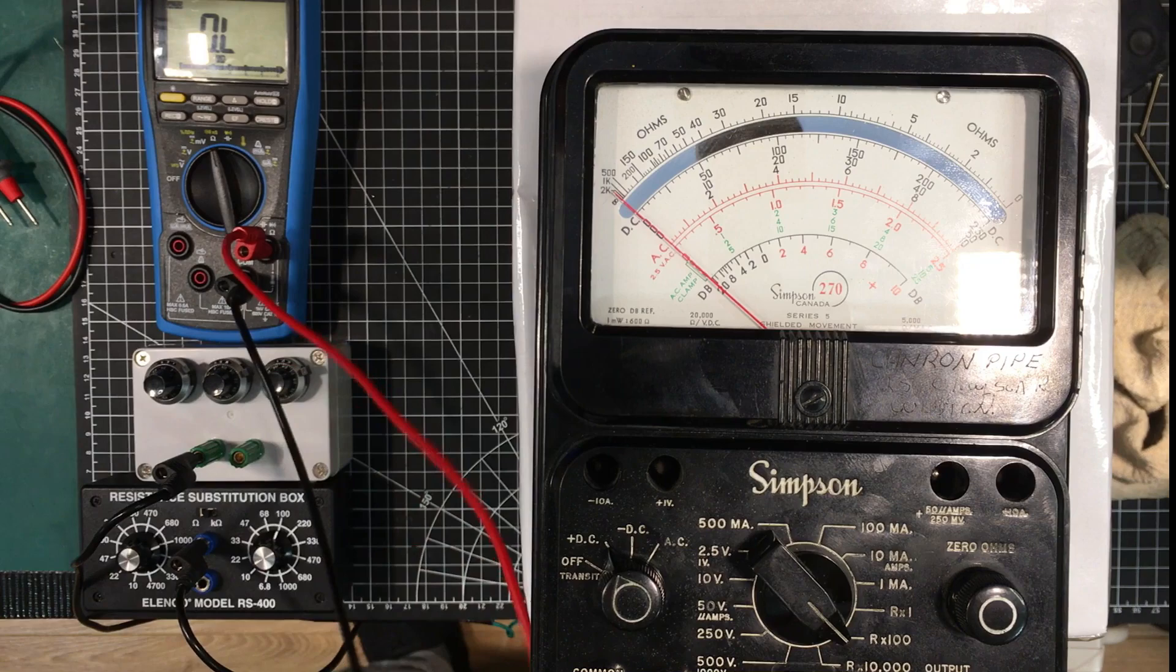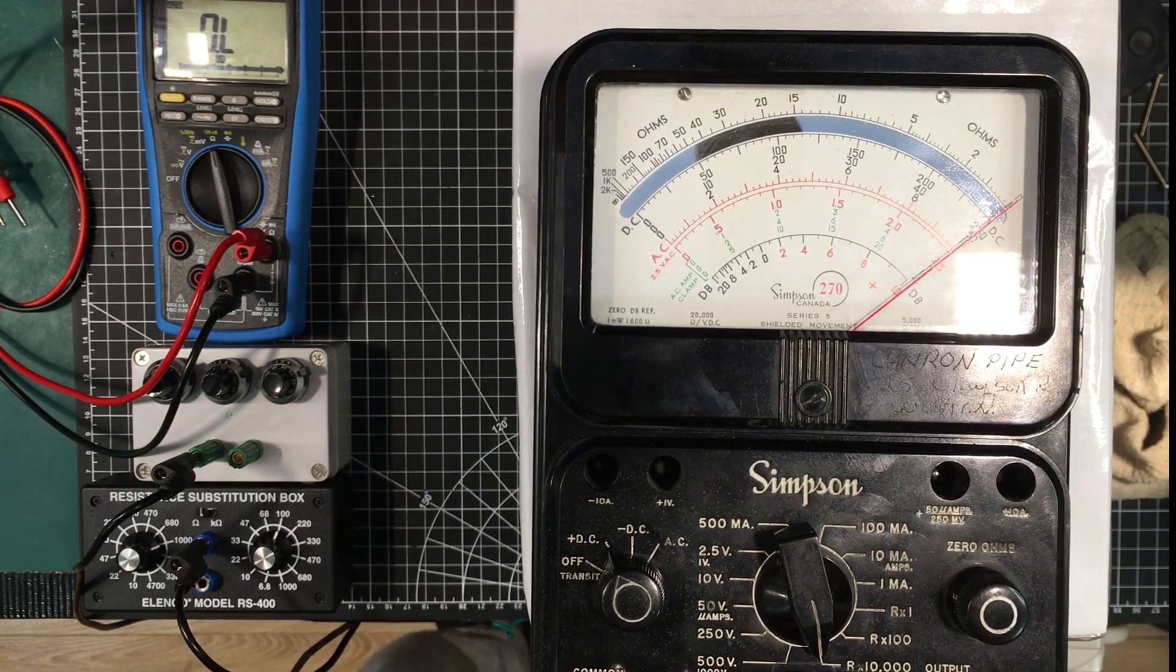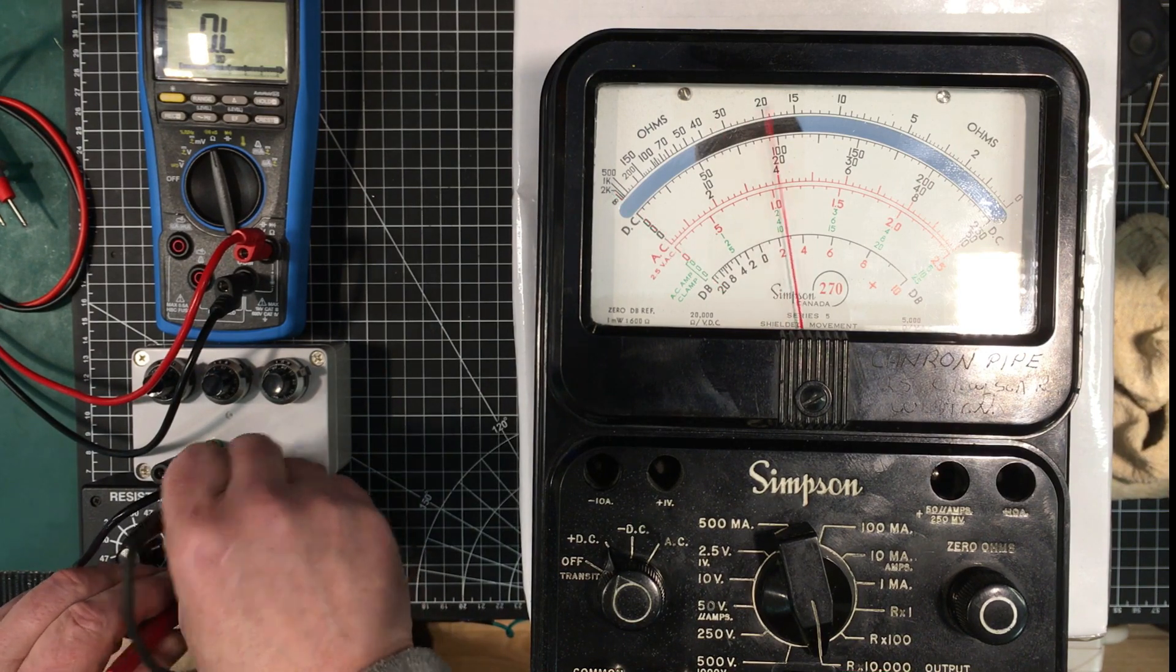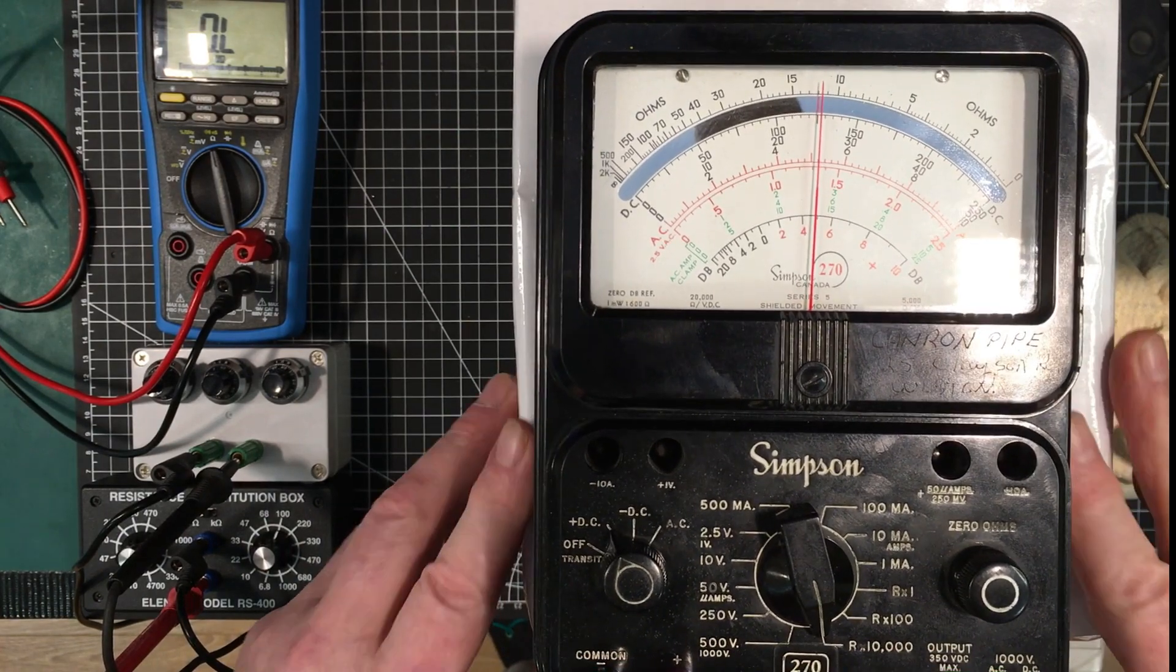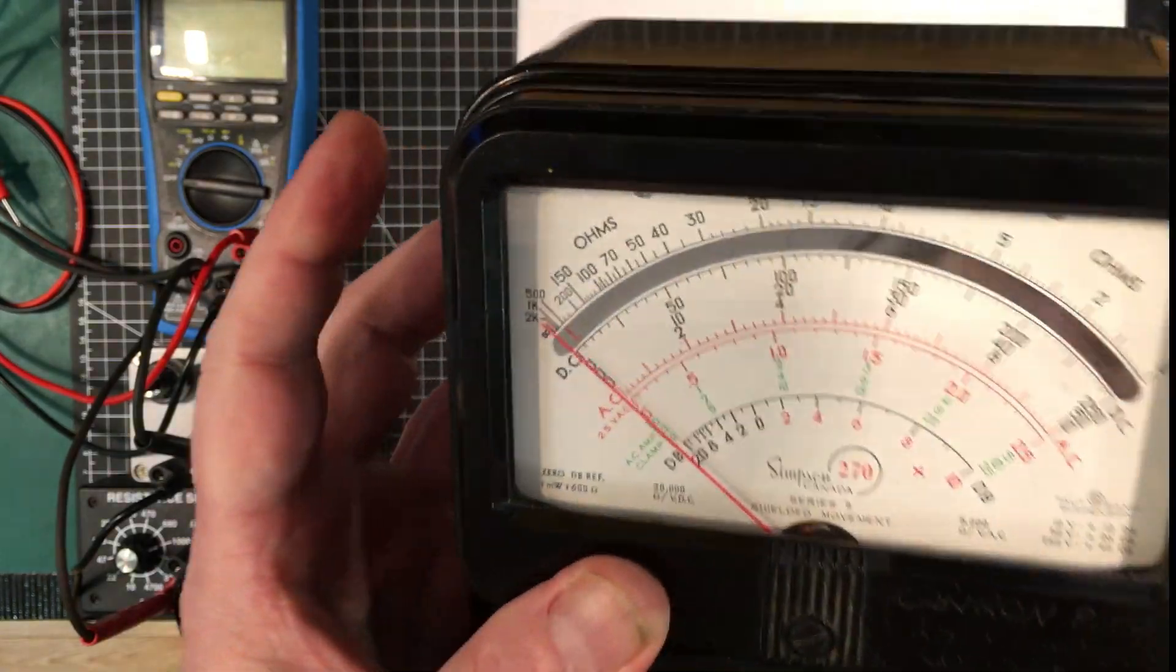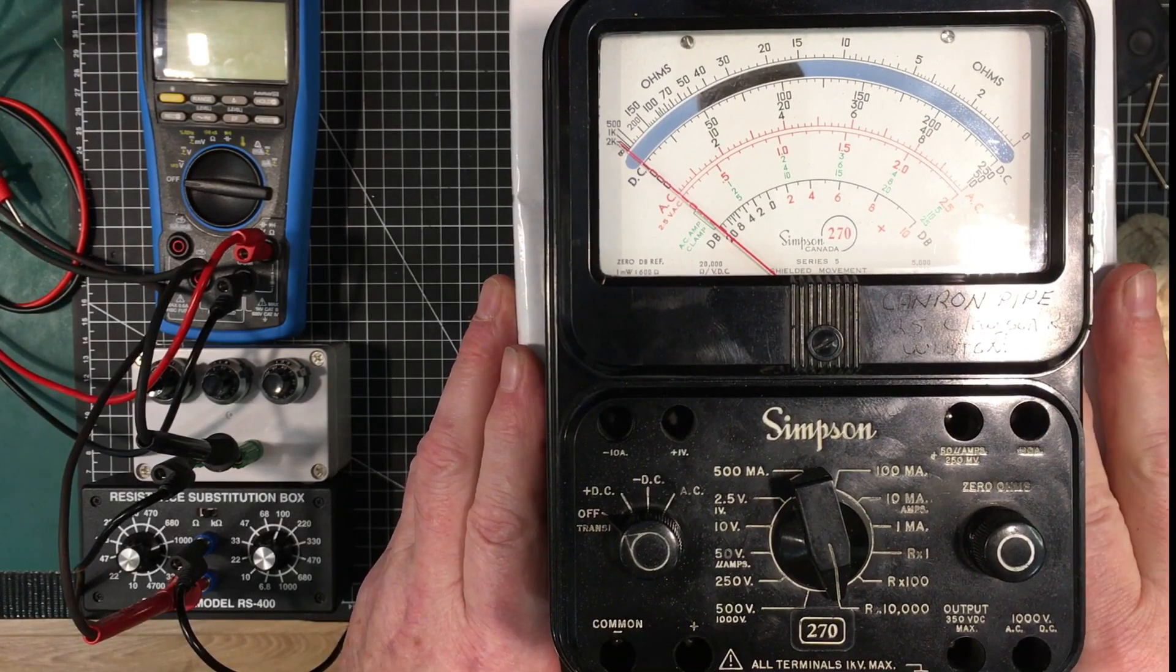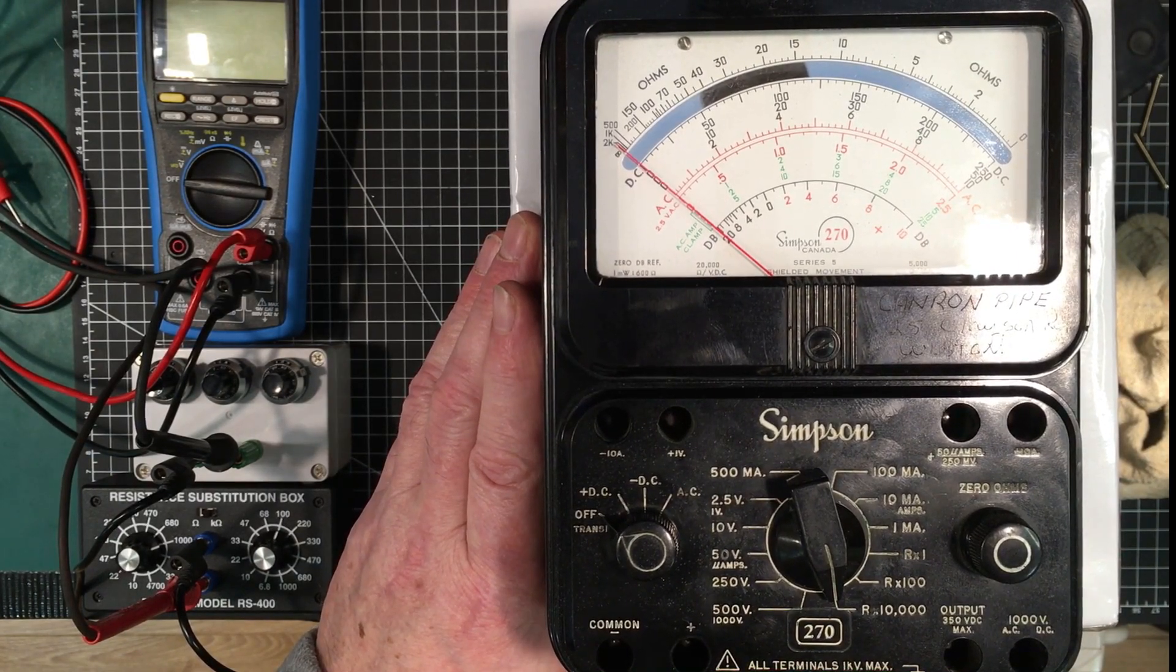We're just a smidgen under 1200, about 1190, maybe 1180. That's well within the specification. The next range up would be 120k. This one is supposed to be from 113,000 to 126,000 within the reading area. We're well within there, it checks out from top to bottom. We didn't have to adjust anything. Forty years of abuse and neglect and it's right on. I will use this meter whenever I need an analog meter. There obviously is a reason why these are famous meters and why they still fetch a pretty penny today. They're just good solid meters in every respect. Thank you very much for joining me today, bye bye.